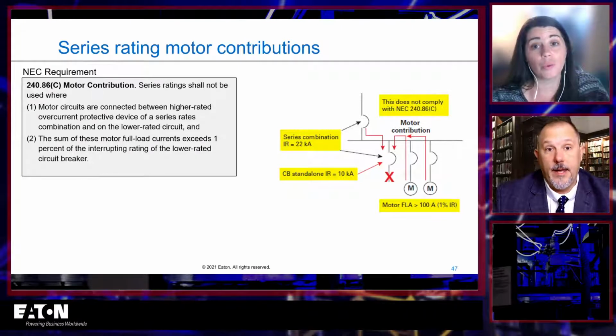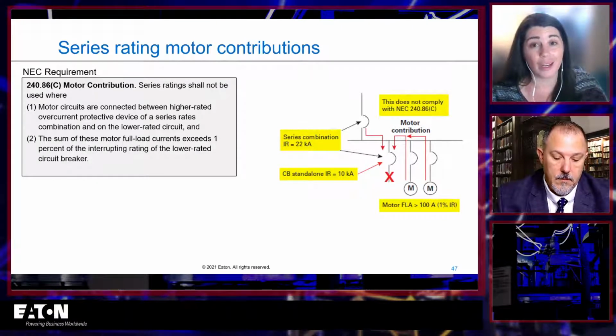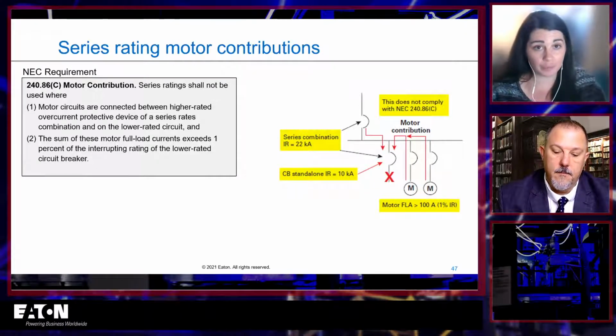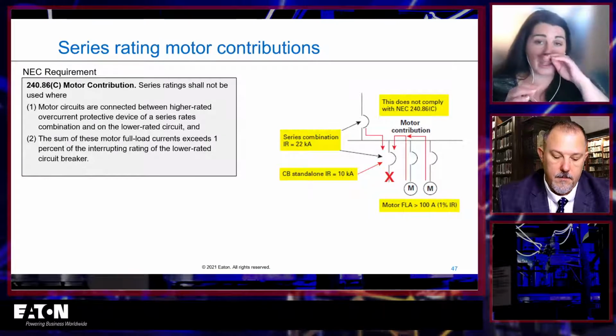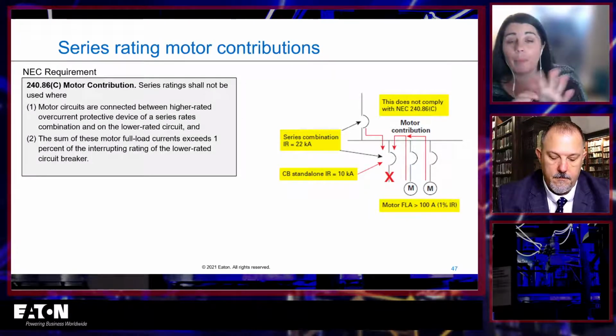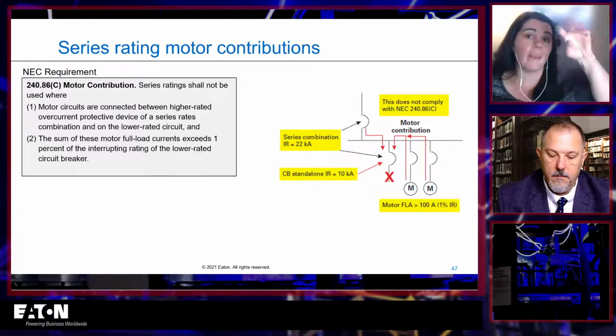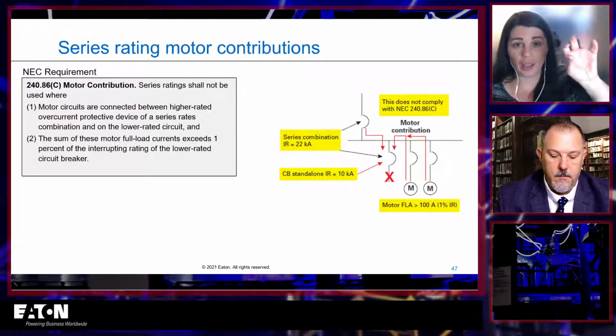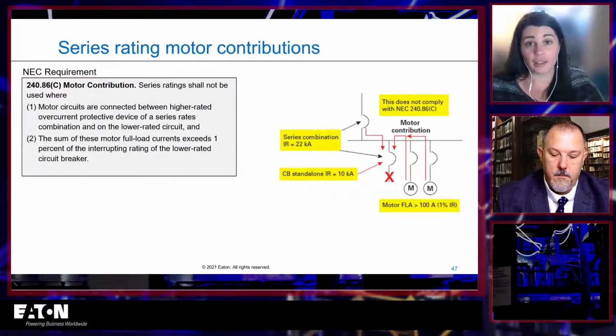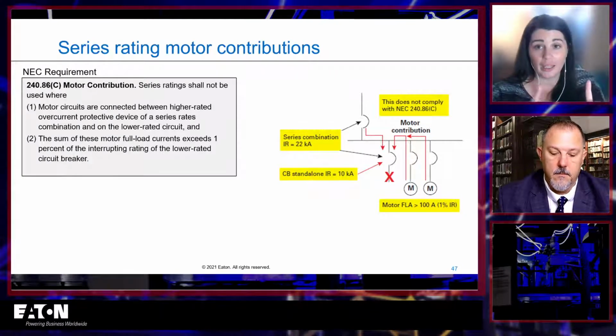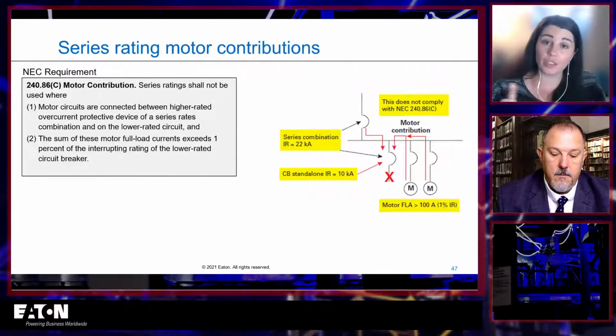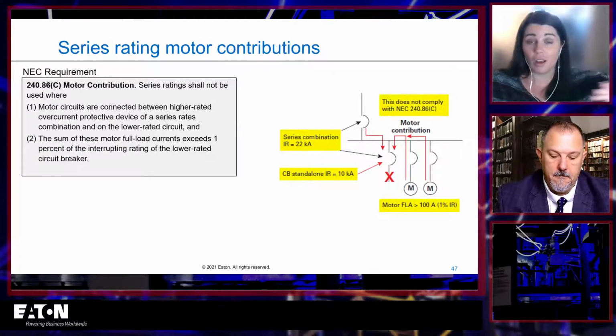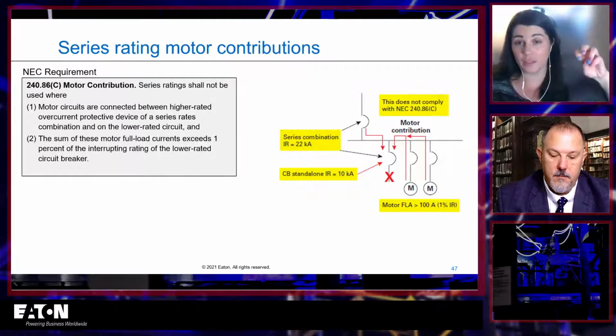Yeah. So another thing, and a reason why we typically can't series rate industrial control panels, is because there are so many motors involved. When you have motor contributions, think of this as a panel board with a main breaker, and that main breaker is 22 kA, and all of the branch breakers are 10 kA.